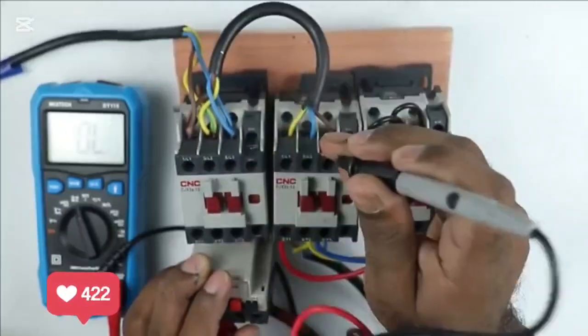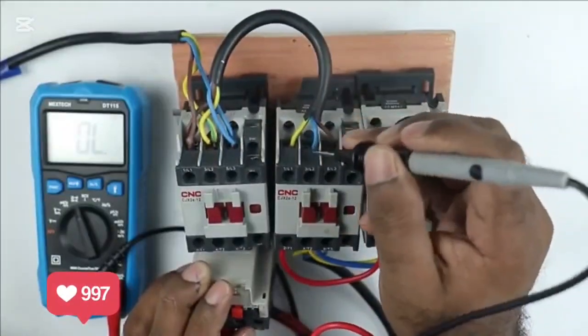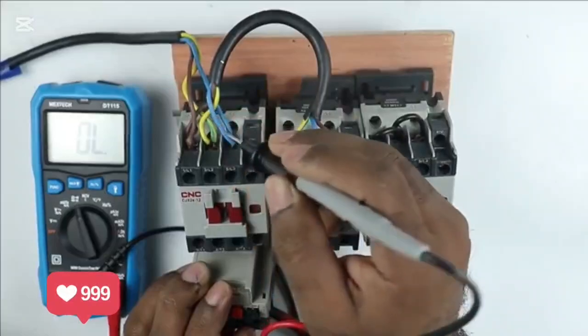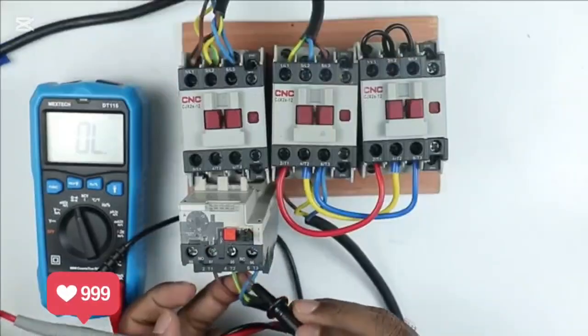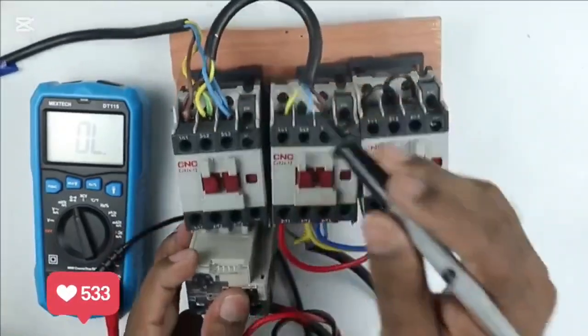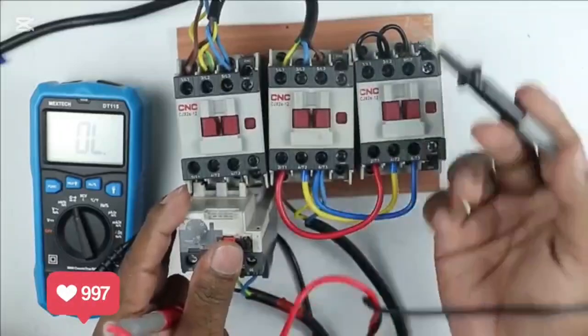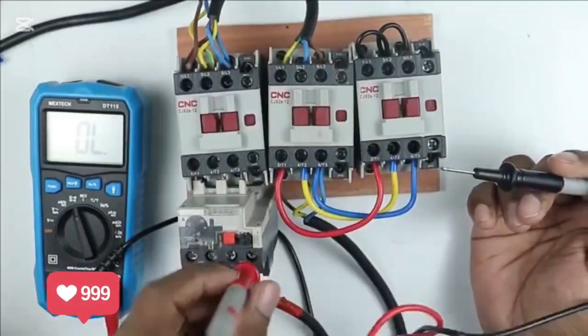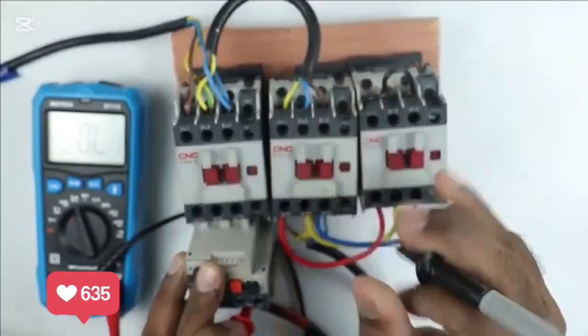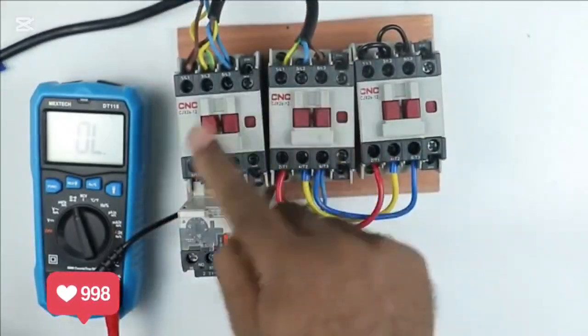After connecting the probe, turn on the contactor. I am getting continuity here. Blue wire is connected here. And here also blue wire is connected with blue wire. It means here it is Y phase and here it is B phase. So this winding will also get two phase power supply. Let's check for the third wire also. After connecting probe, check for continuity. We are getting continuity. It means everything is perfectly alright.